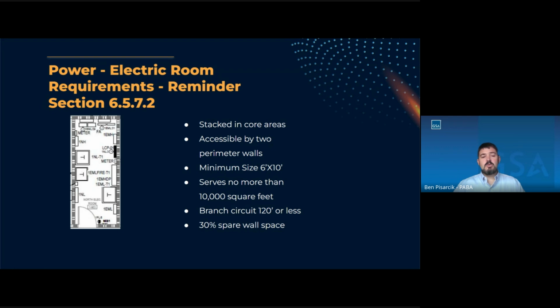They have to be accessible by two perimeter walls. What else do we find in core areas? We find elevator shafts, mechanical shafts, things like that. And if that electric room is completely surrounded by shafts or other walls that you can't penetrate with conduit to feed those loads, then it's not helpful. So they have to have two walls to penetrate. Minimum size 6x10. That's a good rule of thumb. Obviously, they can be larger, but that's the minimum size of an electric room.